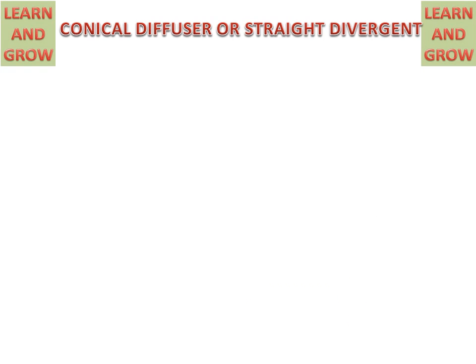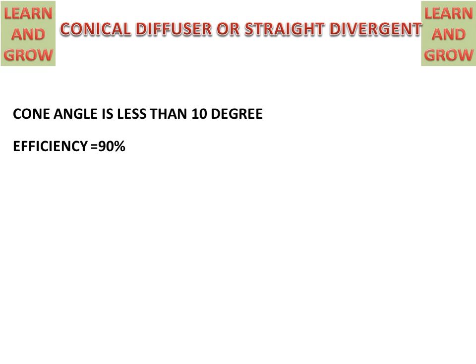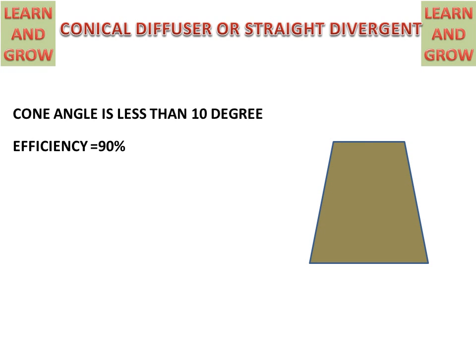Conical diffuser or straight divergent type of draft tube. The cone angle will be less than 10 degrees, because if the angle is too high then cavitation will occur. Water will enter from the upper side and exit from the lower side. This cone angle must be less than 10 degrees.